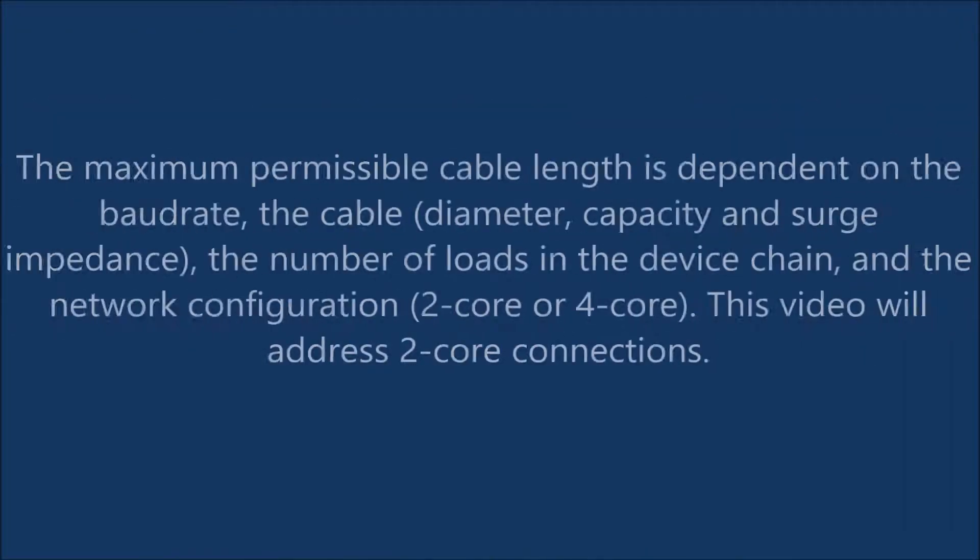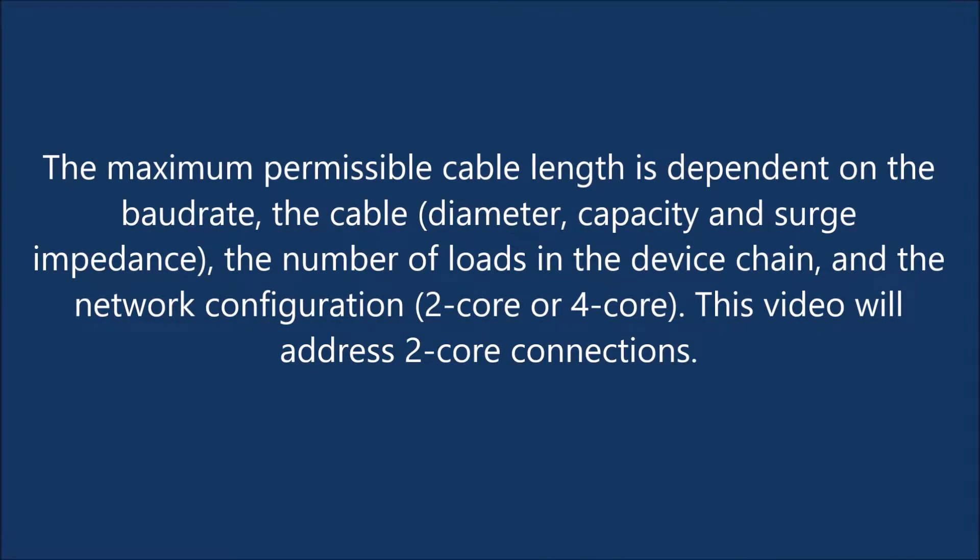The maximum permissible cable length is dependent on the baud rate, the cable diameter, capacity, and surge impedance, the number of loads in the device chain, and the network configuration — 2-core or 4-core.